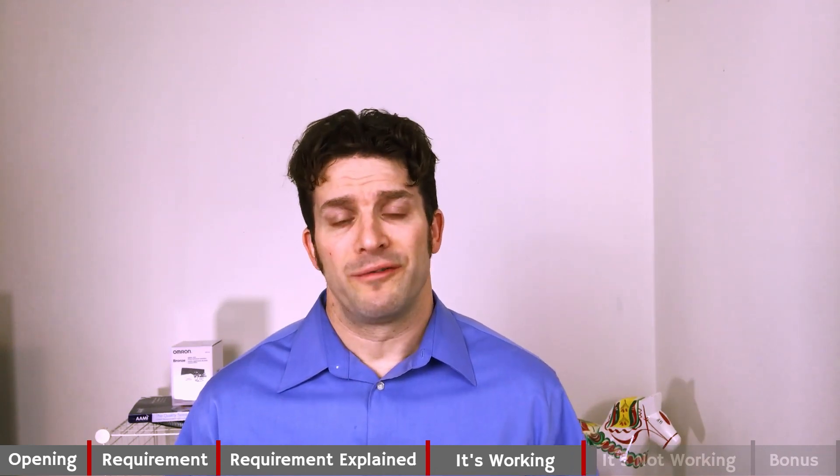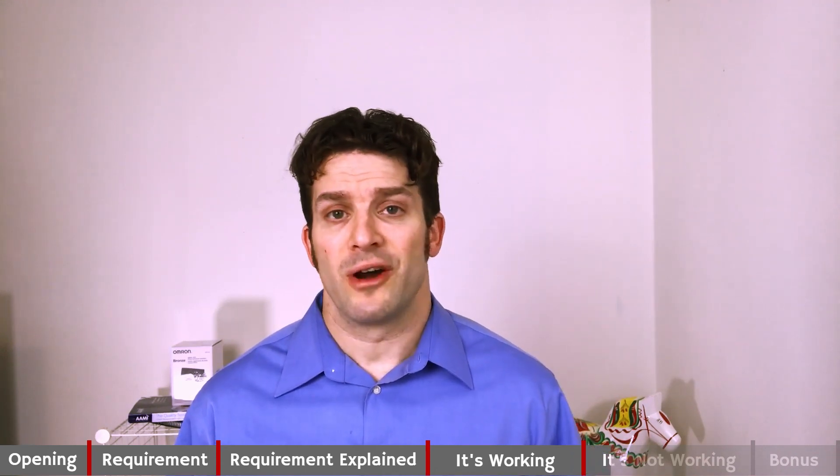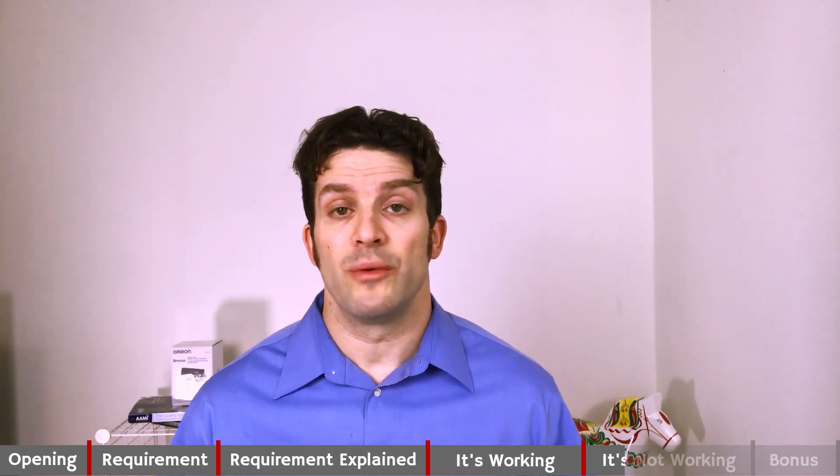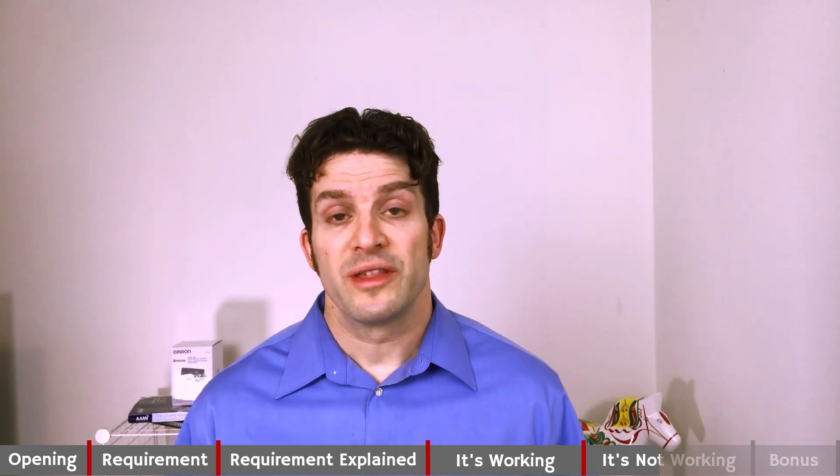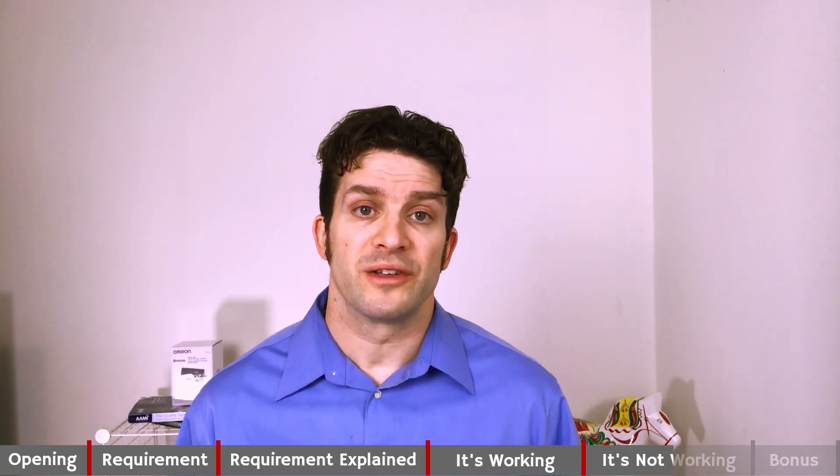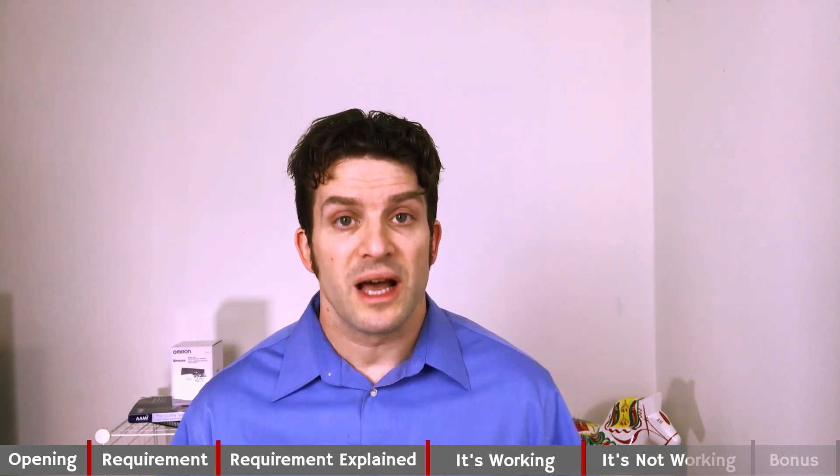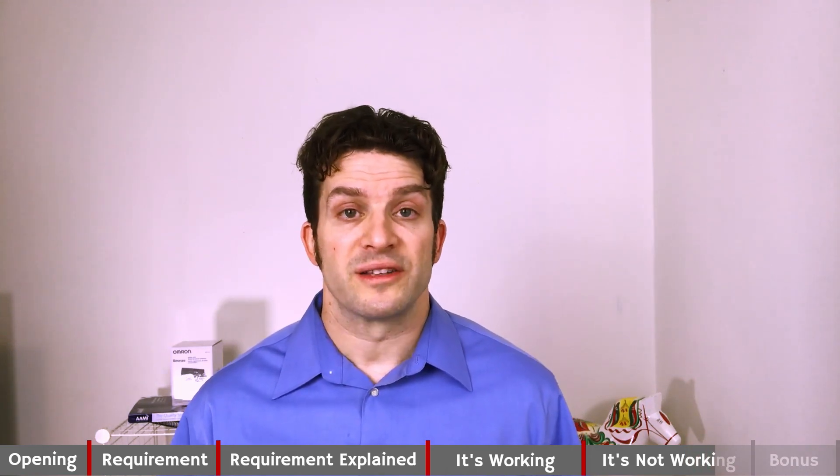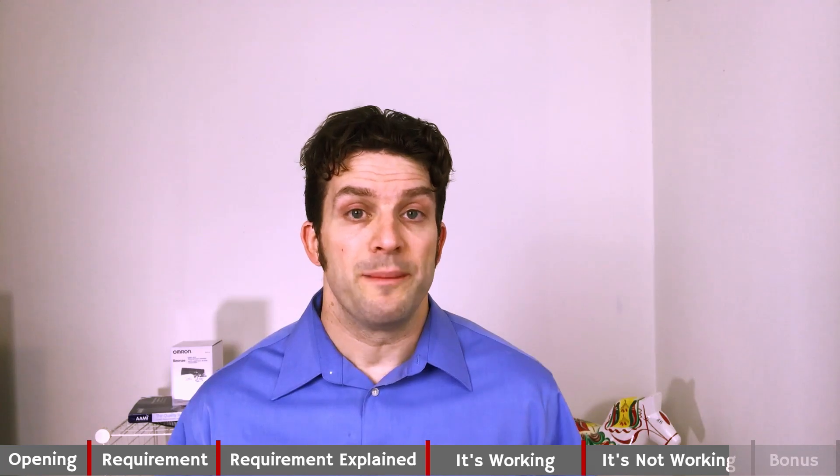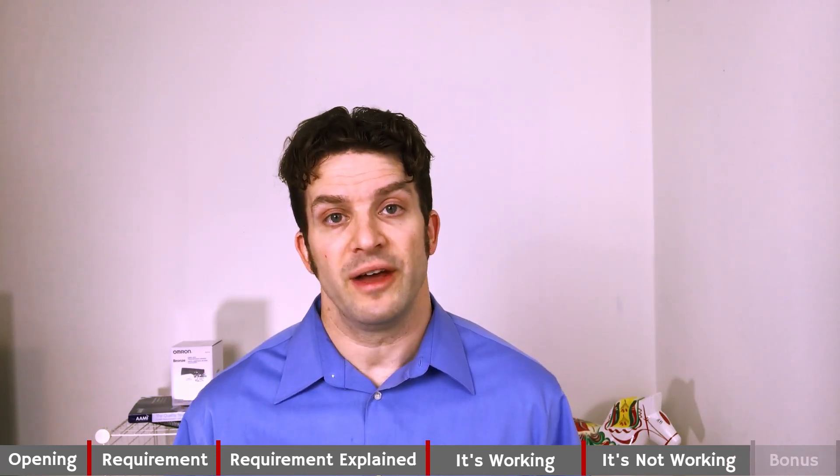How do I know it's not working? Well, first, our complaint rates, our adverse events, they're higher than what we estimated in our risk management documents. Second, we have recalls within the first two years of product launch related to the design and safety of our medical device. And then finally, during audits of our design history file, we get major non-conformances, critical major non-conformances that are found.